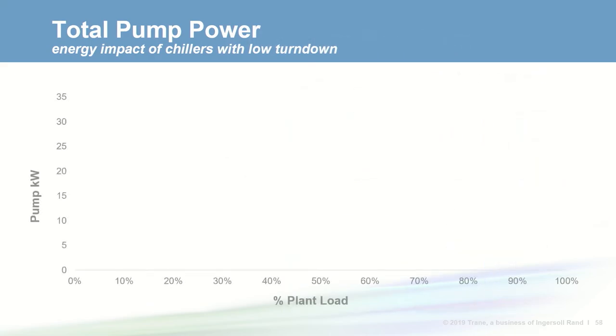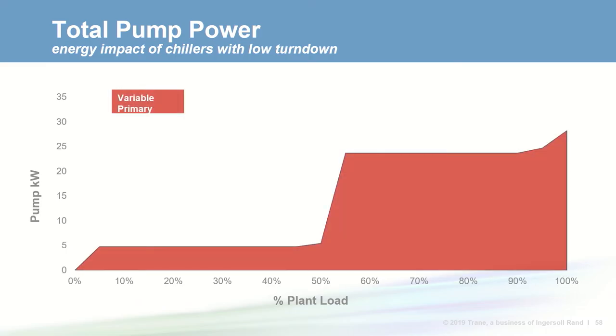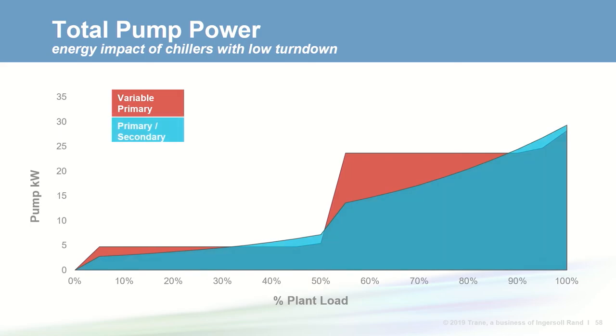Looking at total pumping power based on plant load: for variable primary flow, there are two large plateaus of pumping power due to the high minimum flow — as building load decreases from 90 to 55 percent and from 45 to 5 percent, the system must bypass flow to maintain minimum chiller flow. The primary secondary configuration shows the impact of being able to reduce distribution pump GPM to match building load. The variable primary variable secondary configuration follows the same trend as primary secondary but further reduces primary GPM to save slightly more pump KW. Because of poor chiller turndown, there are numerous plant loads where a variable primary flow configuration will cost more energy.